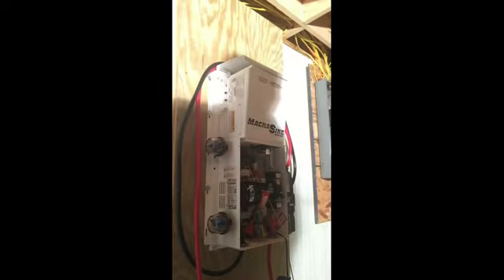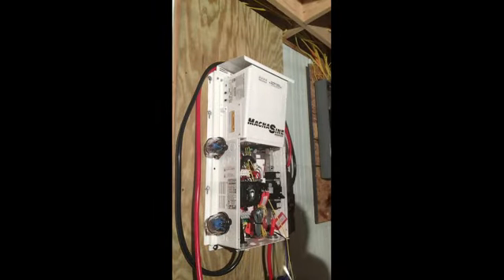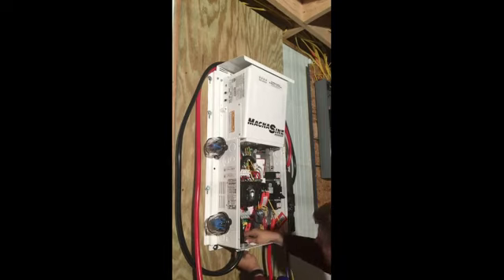And then I fired up the generator again and put 110 volts onto that bar and turned each circuit breaker on one at a time and then tested all the fixtures and all of the plugs that were correlated to that circuit breaker. That's how I knew that the house was wired correctly and that I was ready for solar panel hookup. Again, you're not going to do this. This is just ancillary information that I'm giving the students on how I ensured that my house was wired properly and also that every switch, socket, light, and fan was working.